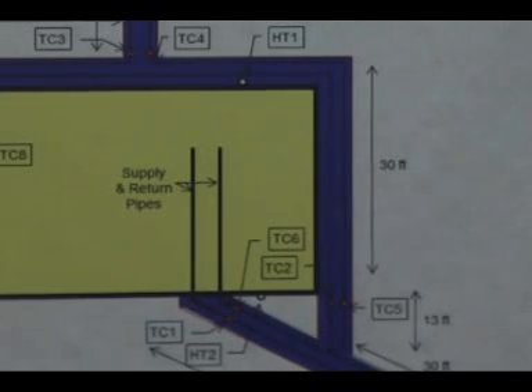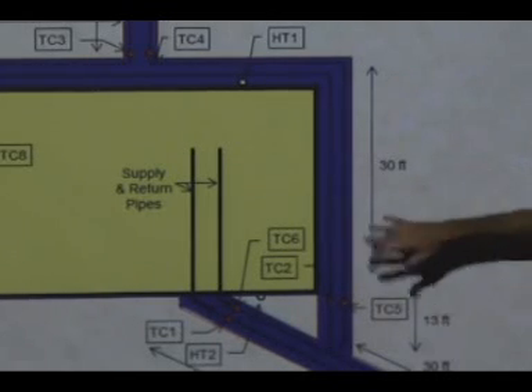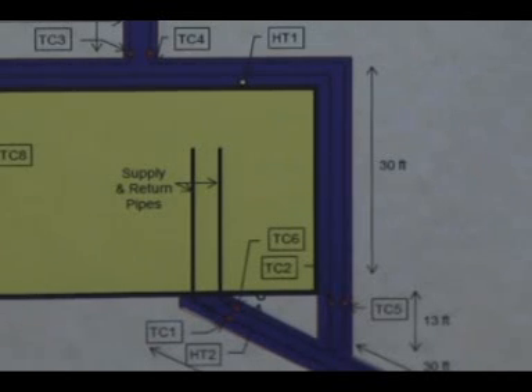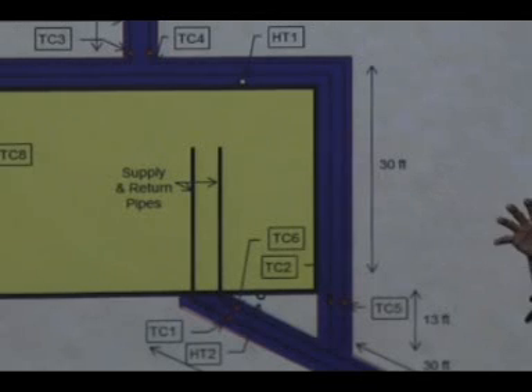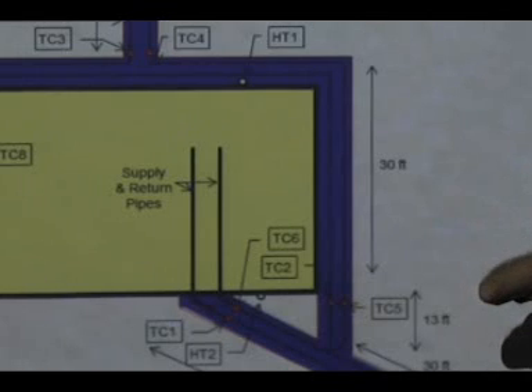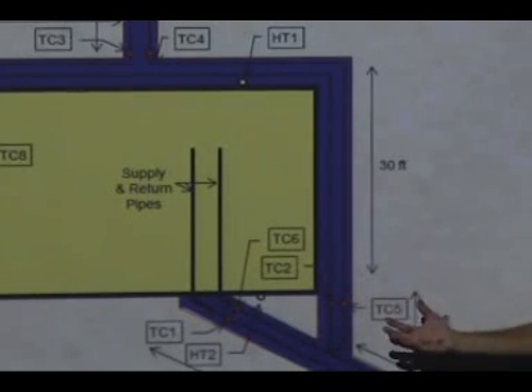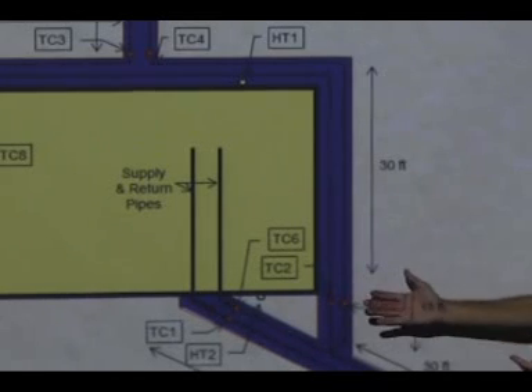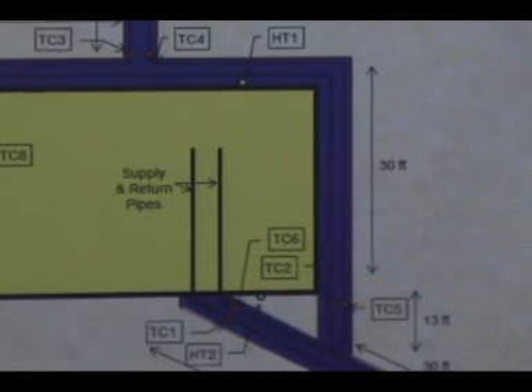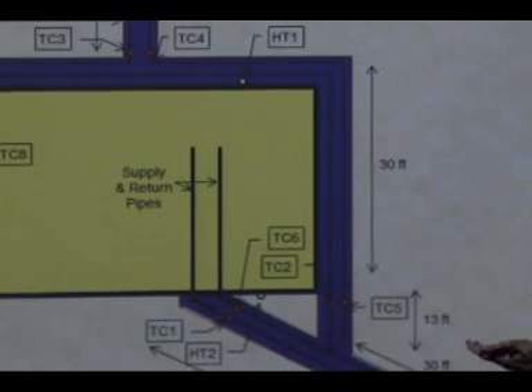This is just the layout. When people talk about temperatures at 5 feet being 55 degrees, I've measured these temperatures since 1982. These surround the pipe, and especially in summer, if you don't size everything correctly, as you take heat out of the house and dump it into the ground all summer, you get what we call hot loops this time of year. It's no longer 55 degrees because you've been throwing heat in there all summer, and this summer a lot was thrown in. The return temperature can actually be up around 90 degrees, so that soil immediately around the pipe heats up, and the efficiency falls off as the season goes on. You have to be aware of that to size these systems right.